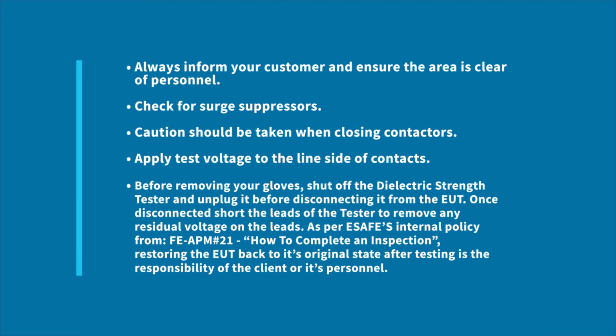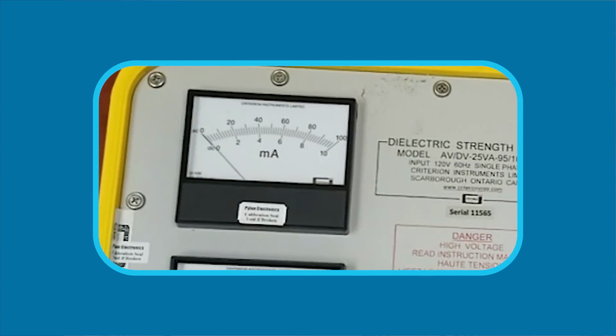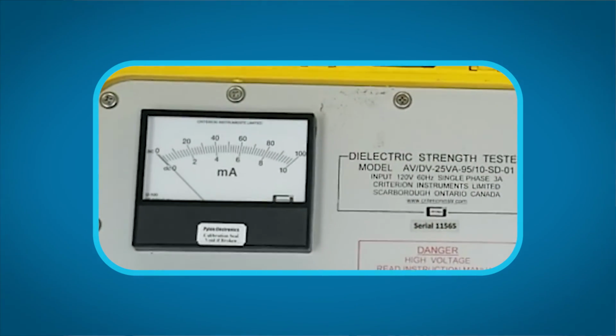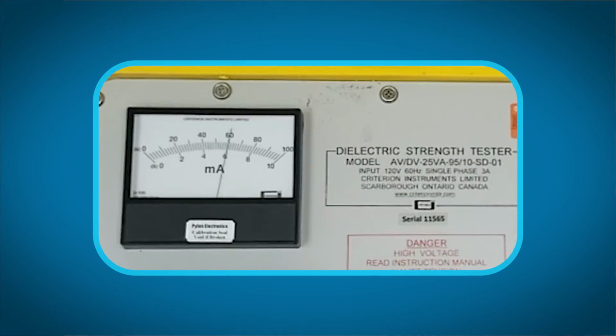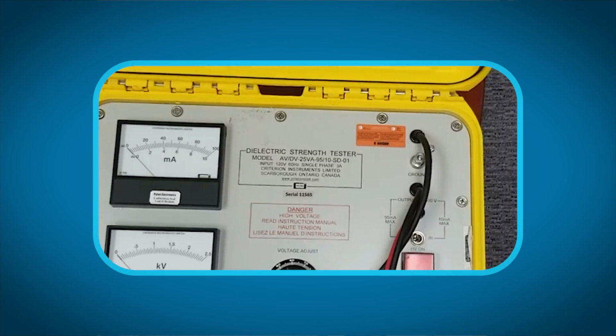As per ESAFE's internal policy from FEAPM number 21, how to complete an inspection, restoring the EUT back to its original state after testing is the responsibility of the client or its personnel. The test is passed if there is no insulation breakdown as indicated by the tripping of the current relay on the dielectric strength tester.